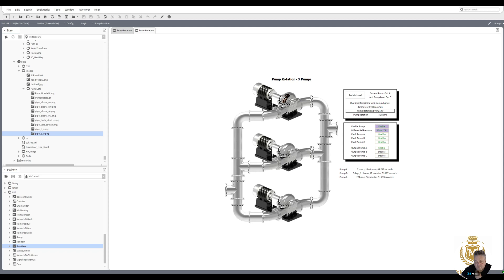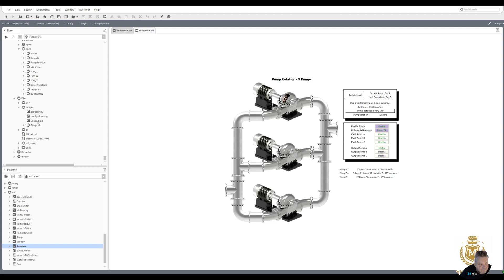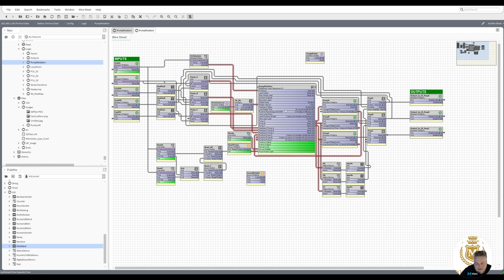Welcome back to the N4 Learning Channel. I've just done some graphics for the three pump rotation. I've set the pump rotation for every hour and it's got three minutes left, and we're running on output pump A at this moment in time. If you remember, about two or three videos ago we basically made a pump rotation using a rotational load sequencer and we added all these blocks to it.